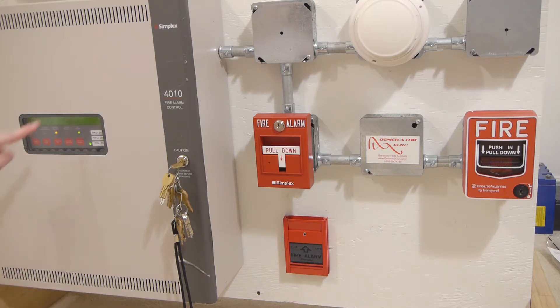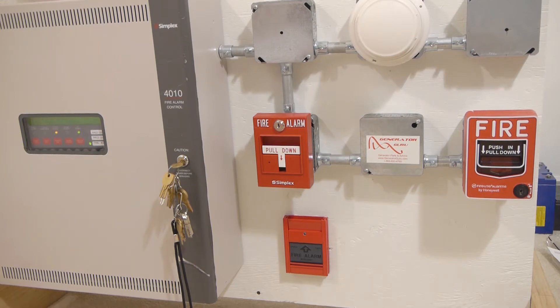As you can see here I have my Simplex 4010 demonstration board and there's one trouble in the system right now, a negative earth ground fault. One thing I do like about Simplex is they do tell you if it's a negative or positive earth ground fault.